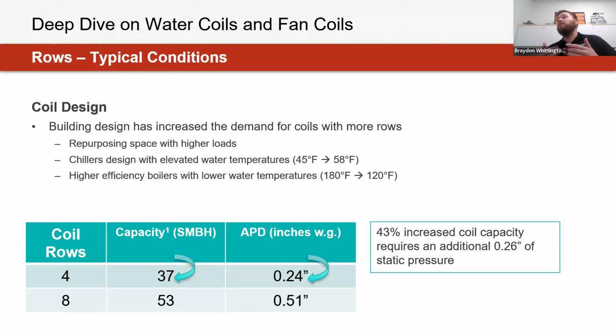But with that, as we start to increase the overall rows on a coil, it's also adding additional air pressure drop, or resistance, that the coil is going to be adding to our system, or that the fan is trying to compensate for too. So even, for example, another 1/4 inch of static that a fan is trying to compensate for, in a lot of cases could be significant for trying to achieve the same results, especially when we're looking at retrofit applications too.